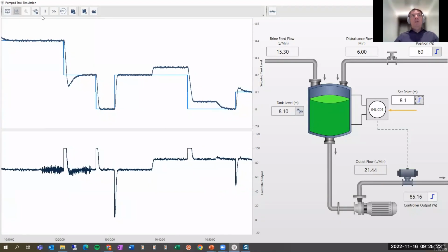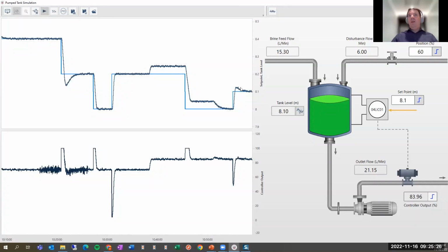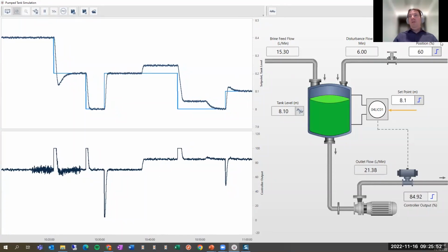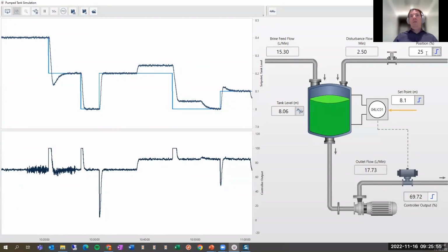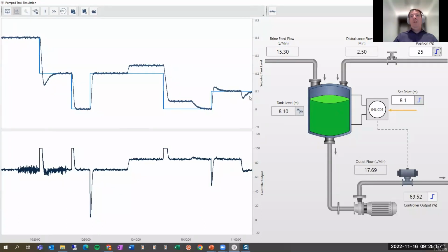Okay, so it's like that. You need to tolerate overshoot. But remember here, all the things I've been doing are set point changes, right? And it's pretty rare that you change your set point in your tank. Usually you say, I try to maintain 50%, and I allow a little bit over, a little bit below, and it will absorb the disturbance getting into your systems. So we'll keep the aggressive tuning, and we'll do a disturbance here, and we can see the rejection.